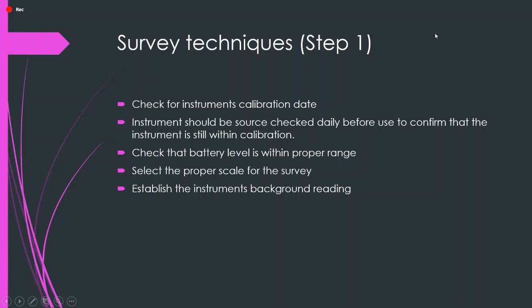The next thing you should do is select the proper scale for the survey. If it's a low level area, you can select the lowest range. If it's a higher level area with a higher background, that's where selecting a certain range makes the biggest difference. If it's really low levels, you can turn on the lowest range and pick up really well. But if it's going to have a really high background, maybe that instrument wouldn't be a good choice for detecting what kind of contamination you're dealing with. Our final bullet point is to establish the instrument's background reading. It's always good to know where that sits and keep it in mind, because when you're surveying an area for contamination, if the reading is about twice background, then that area or item is contaminated, and you should follow the proper procedures from there.